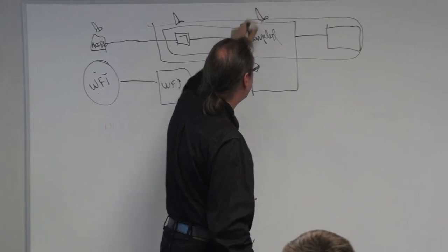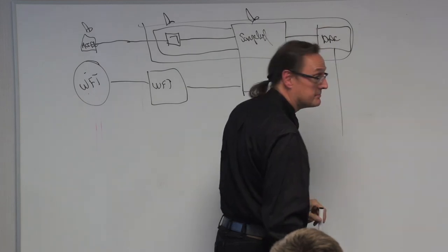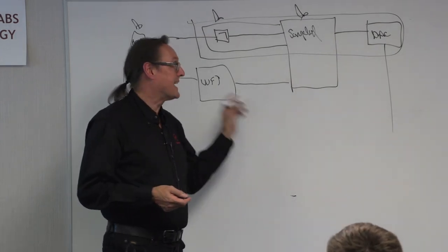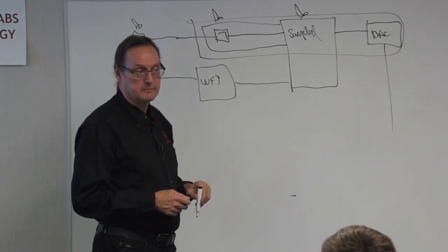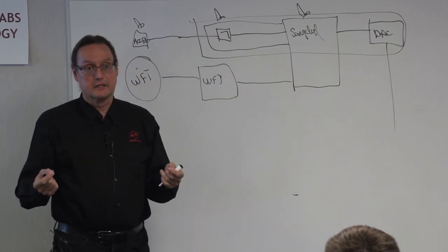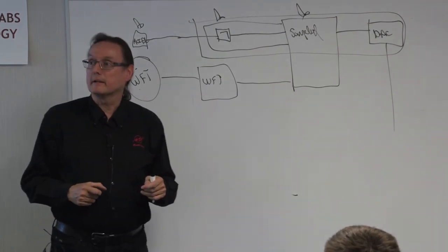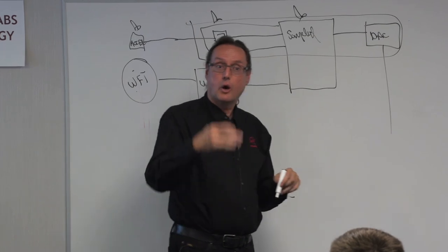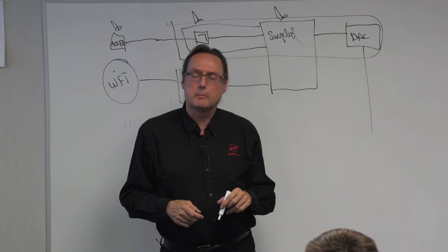In almost any system doing closed-loop control, this chain can never be fast enough to compensate for loop delay and have a stable system on its own. There are guidelines: you want to be at least 10 times faster than what you're actually trying to control. In a Titan system, the total end-to-end delay is about 30 milliseconds at 512 Hz with a 100 Hz filter. When you do a simulation with any simulator, you have inner loop and outer loop control — the outer loop involves this data path, while the inner loop is your driver to actuator with tight feedback, controlled to move a specific amount within a given tolerance.